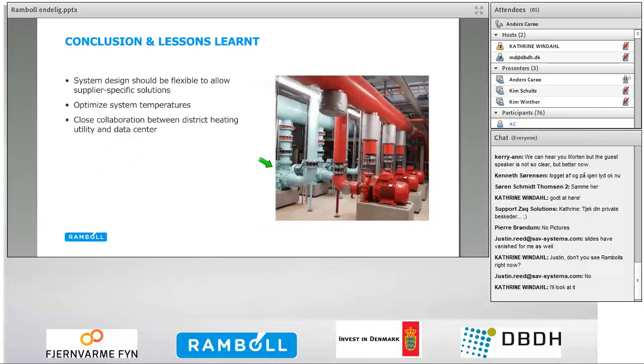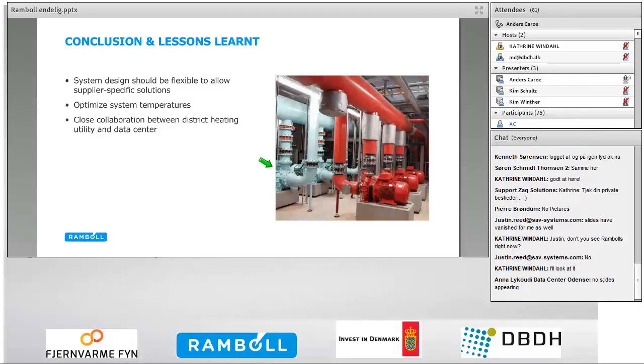So one of the key takeaways from this project has been to design a system with a certain amount of flexibility, because the different heat pump suppliers can offer different solutions that can achieve similar results. Therefore, it's important to make a design that allows them to offer the best and most efficient solution within the functional requirements and within the equipment that they can offer. Also, the temperature difference and the temperature lift between the waste heat recovery side and the district heating side will have a big impact on the system's performance. That might not be a big surprise, but after all, it's still a very important area to focus on.